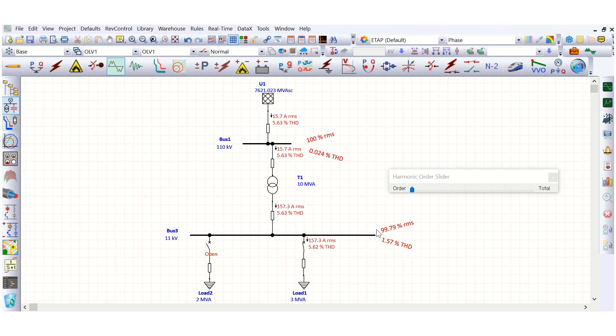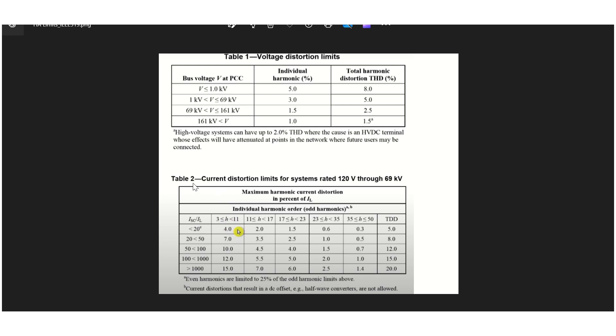If the result still exceeds 5%, a filter needs to be added to the bus. Now moving to the next table, which defines the current distortion limits — maximum harmonic current distortion in percent of IL — listing individual harmonic orders.